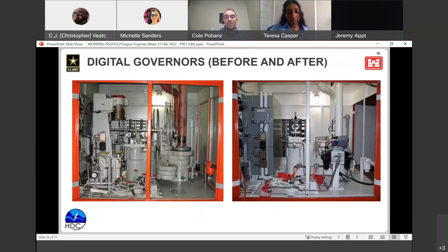Originally we had mechanical governors controlled by mechanical operations such as valves and pistons. Those are decent devices, but it's difficult to attain very high levels of precision with them. So we upgraded, and now most of our projects have digital governors that take up much less area and are easier to troubleshoot. The picture on the left is the mechanical governor - you can see the many valves and pistons used to operate and measure pressure, water flow, and other things in this cabinet. On the right is the upgraded digital governor, run almost entirely on PLCs, and you can see the immense amount of floor space saved just by upgrading from mechanical to digital.